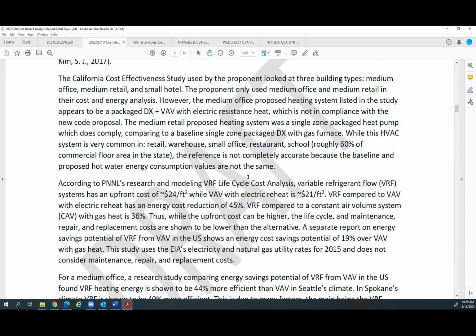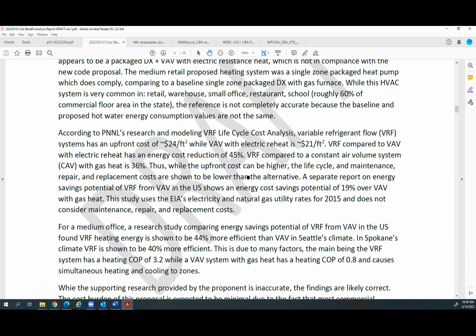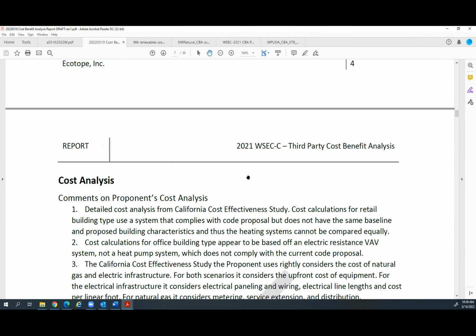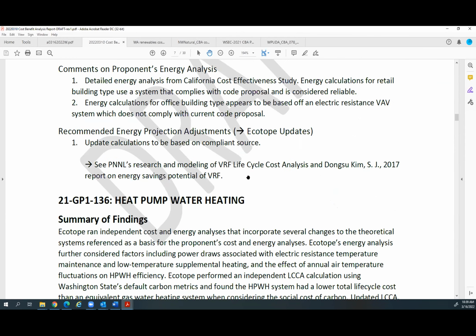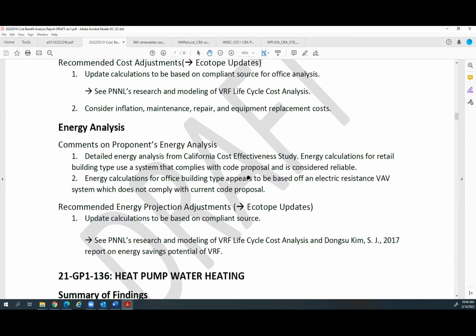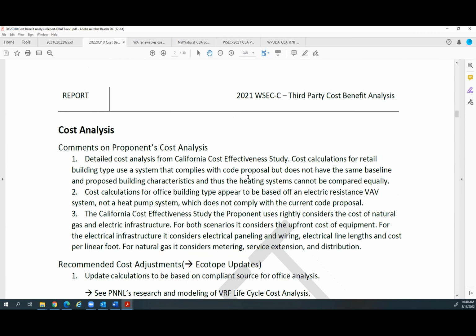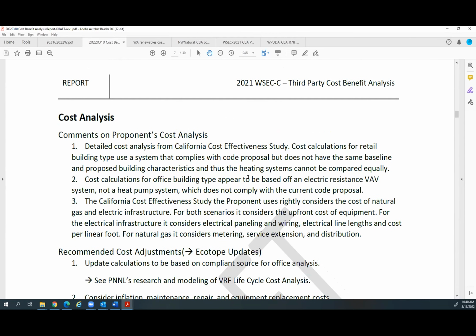So kind of just a comment and observation that I'm seeing here is that with the changes in the current CR 102, it makes it really infeasible to install a VAV in Washington anymore, if you can't use electric resistance heat or a boiler-fueled hot water reheat. So just overall removing another affordable HVAC system option from HVAC designers, and really only allowing a packaged or a split heat pump system or VRF. That's really just an observation there.